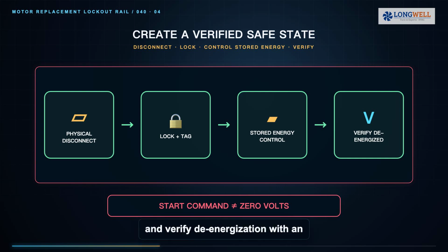directs, and verify de-energization with an appropriate test method. A start command alone does not prove zero voltage. Do not discharge a capacitor by casually shorting its terminals. If the service procedure calls for capacitor testing or discharge, use the specified rated method and qualified personnel. Recheck for multiple feeds, accessories, and control circuits before touching conductors.